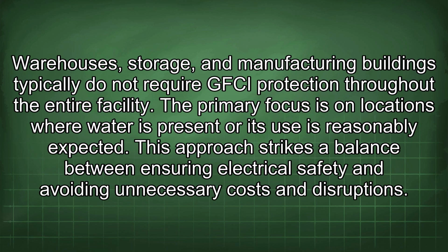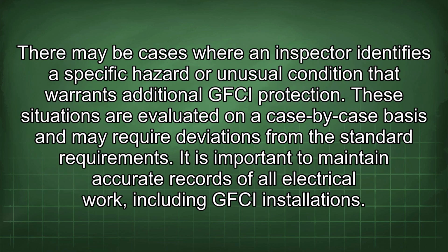Warehouses, storage, and manufacturing buildings typically do not require GFCI protection throughout the entire facility. The primary focus is on locations where water is present or its use is reasonably expected. This approach strikes a balance between ensuring electrical safety and avoiding unnecessary costs and disruptions. There may be cases where an inspector identifies a specific hazard or unusual condition that warrants additional GFCI protection. These situations are evaluated on a case-by-case basis and may require deviations from the standard requirements.